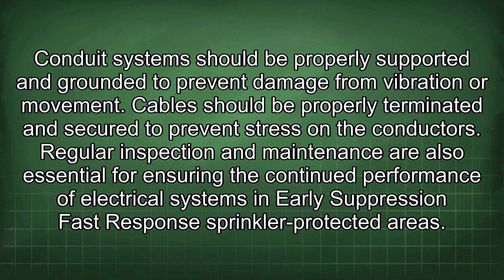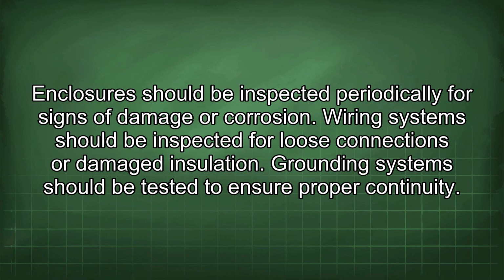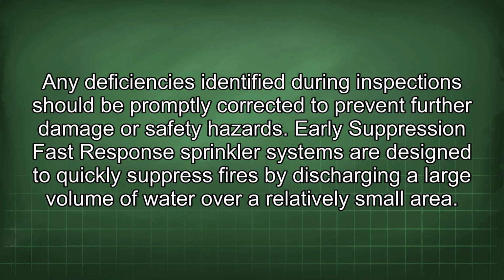Regular inspection and maintenance are also essential for ensuring the continued performance of electrical systems in early suppression fast response sprinkler protected areas. Enclosures should be inspected periodically for signs of damage or corrosion. Wiring systems should be inspected for loose connections or damaged insulation. Grounding systems should be tested to ensure proper continuity. Any deficiencies identified during inspection should be promptly corrected to prevent further damage or safety hazards.